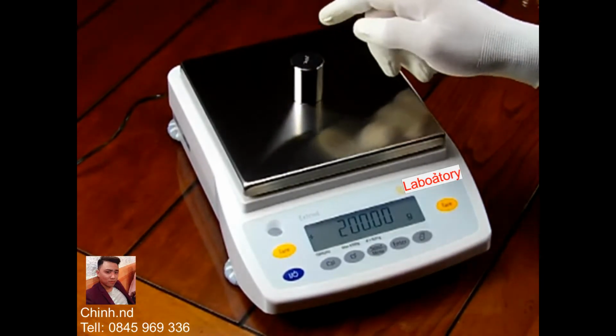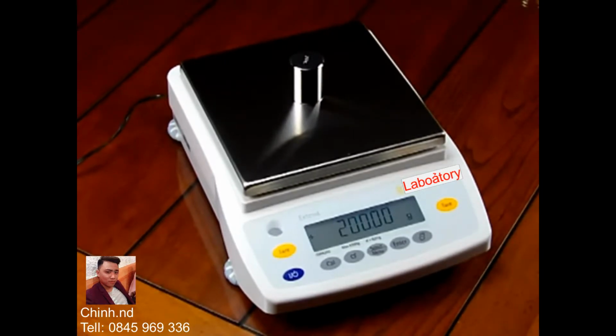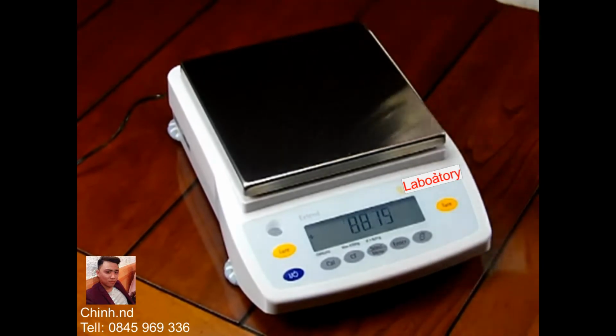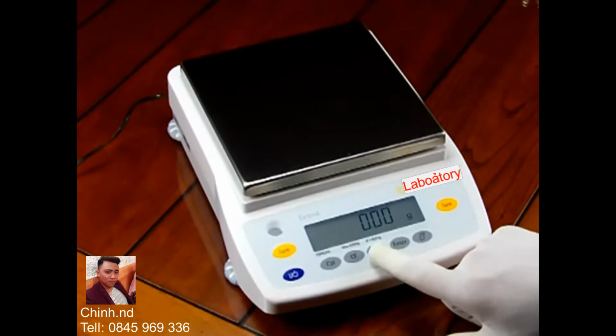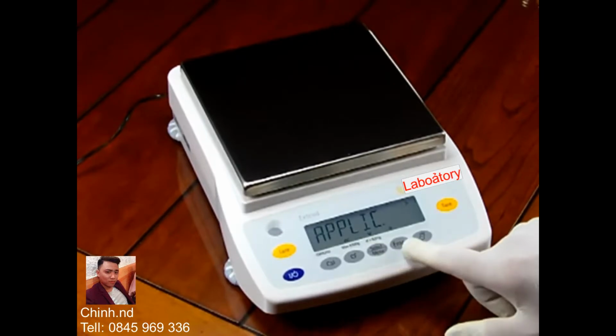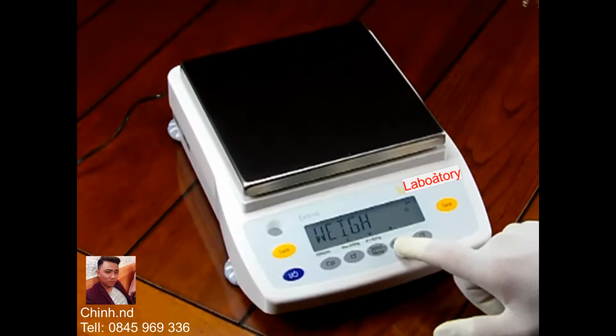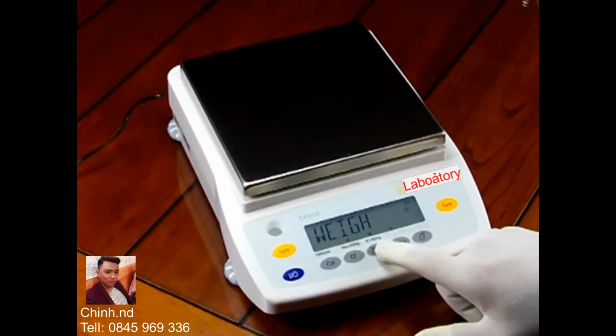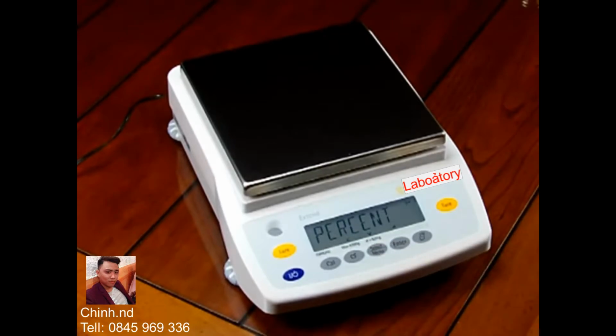Some of the other features that the balance has to offer, you can set this in multiple languages. So if you have staff that speak German, French, Italian, Spanish, Russian, or Polish, the balance can be configured. One simply goes into the menu, and this balance is extremely intuitive. You press down and hold select, and the menu, you can just scroll right through whether you want to set the application, which is we're in the weigh mode, or if one wanted to, you could change that to different units. You have parts count in here. You have percent weigh mode. Percent weigh mode, you would use this if you were trying to obtain a weight readout in percent, which is proportional to a reference weight. So if you were mixing, like for example, 1 pound of ink, and you had a formula, you would use percent mode.